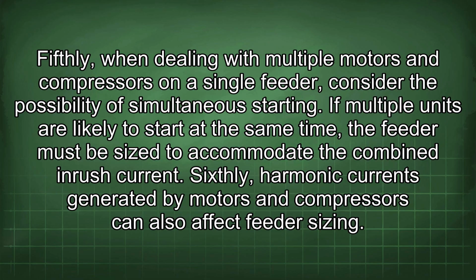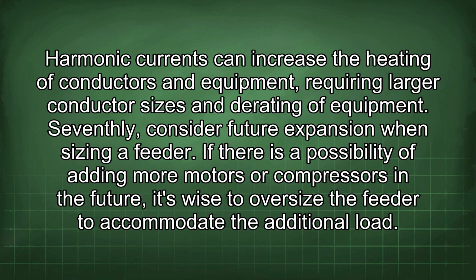Fifthly, when dealing with multiple motors and compressors on a single feeder, consider the possibility of simultaneous starting. If multiple units are likely to start at the same time, the feeder must be sized to accommodate the combined inrush current. Sixthly, harmonic currents generated by motors and compressors can also affect feeder sizing. Harmonic currents can increase the heating of conductors and equipment, requiring larger conductor sizes and derating of equipment.